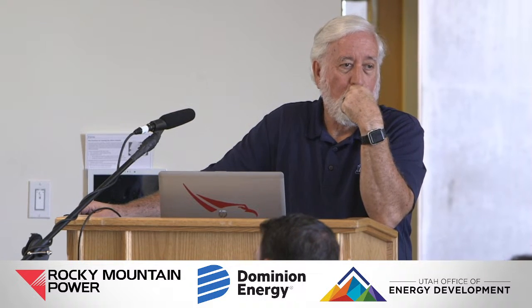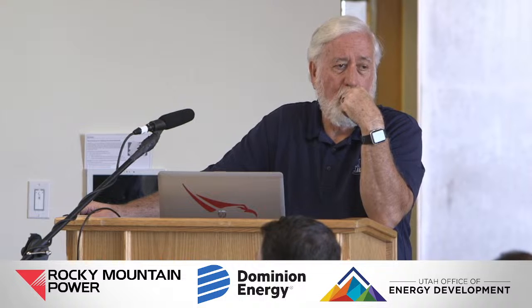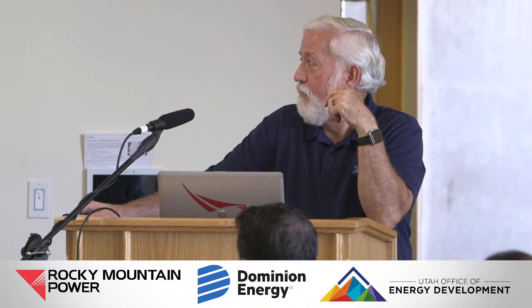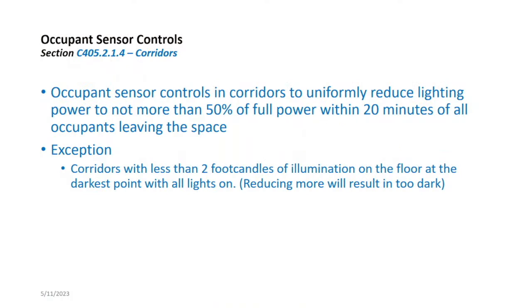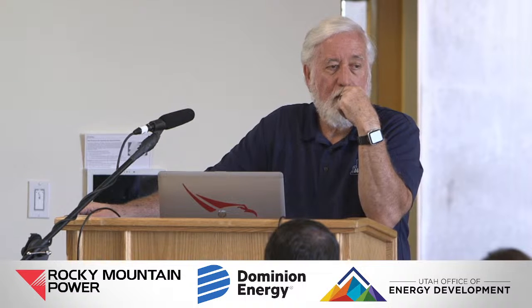One of the things, go ahead, please. Pretty much most of the energy codes, the big three, IECC, ASHRAE 90.1, Title 24, have adopted this language, not more than 50% of the full power. Some people have taken that to mean to turn all the way off. What we've seen across the country now is a lot of the fire marshals, as they're walking the building, are saying, no, you cannot turn these off. You have to maintain minimum foot candle within the building while the building is occupied. So Title 24, actually in the 2022 code cycle, the latest, added wording that at no time shall it be below the minimum foot candle level.